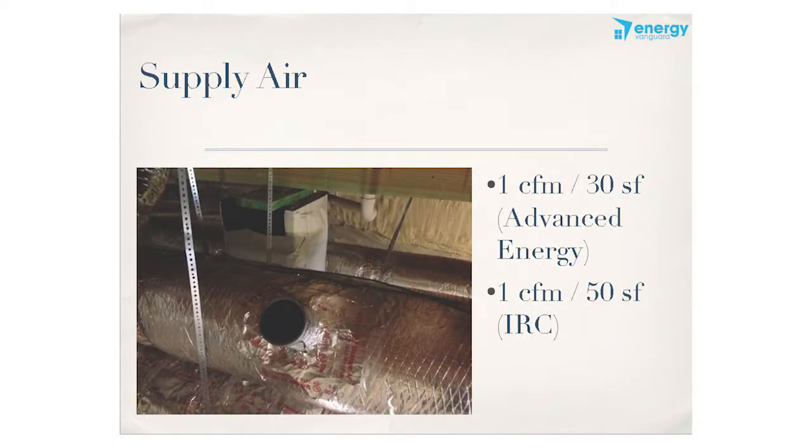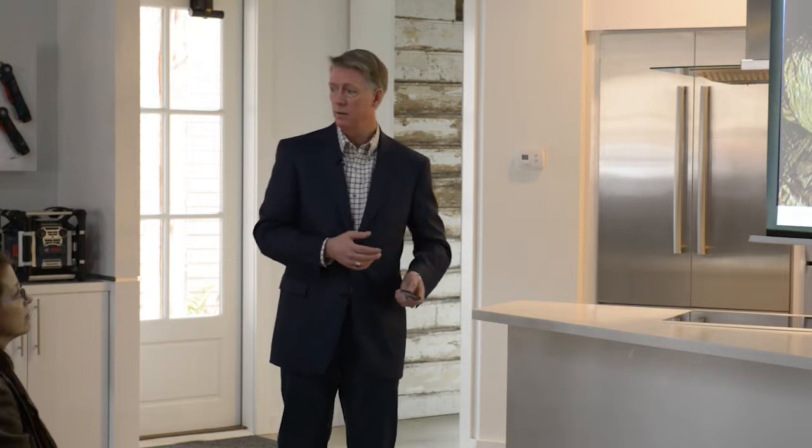And this is that same crawl space we saw before. So this is, when I was there, this was blowing out a nice stream of air. You don't need a whole lot of air in the crawl space. It's a smaller volume of space down there. So typically 30, 40, 50 CFM, cubic feet per minute of air coming out of there. And it helps the area stay nice and cool and dry in the summertime, and a little bit warmer in the winter. So your floors will be warmer if you have this kind of crawl space.